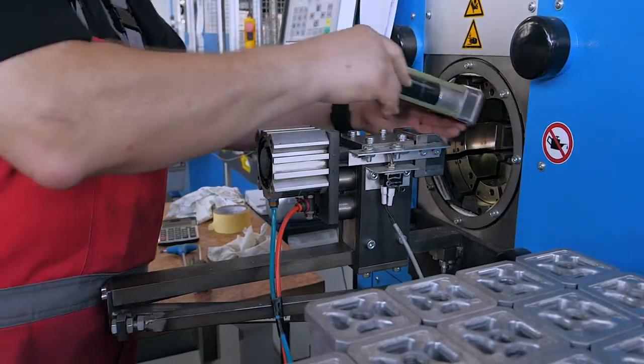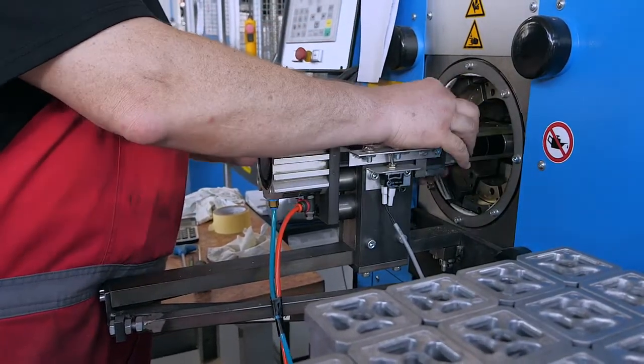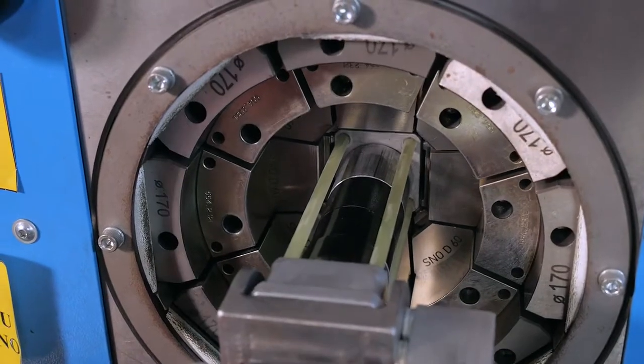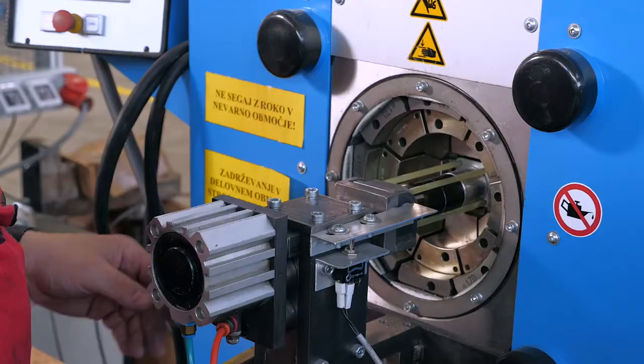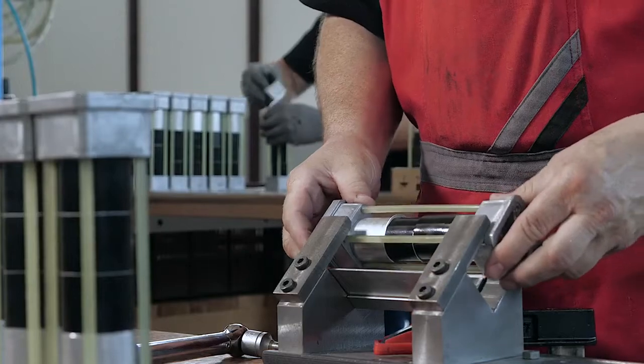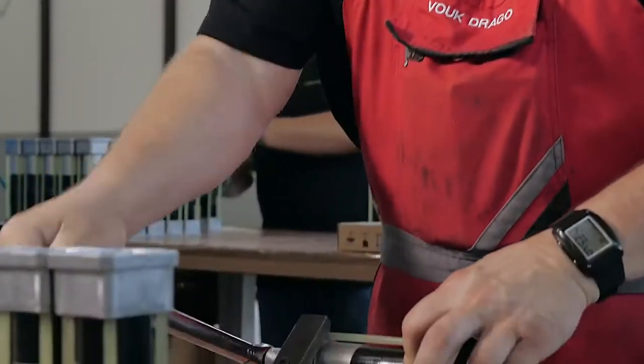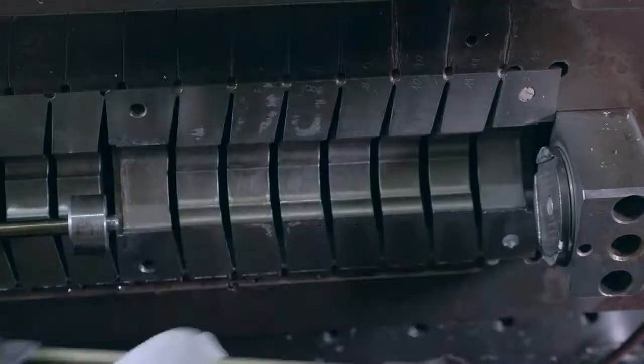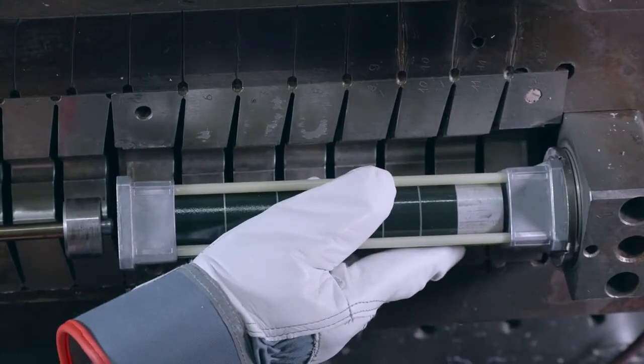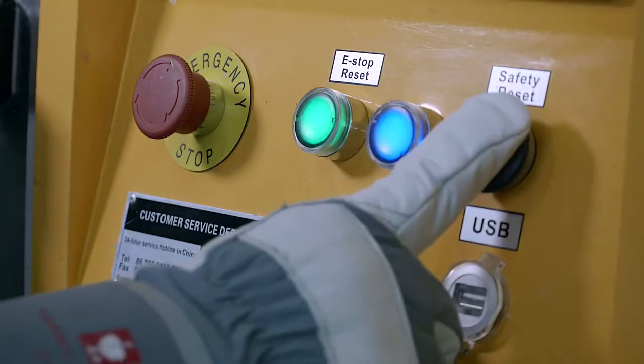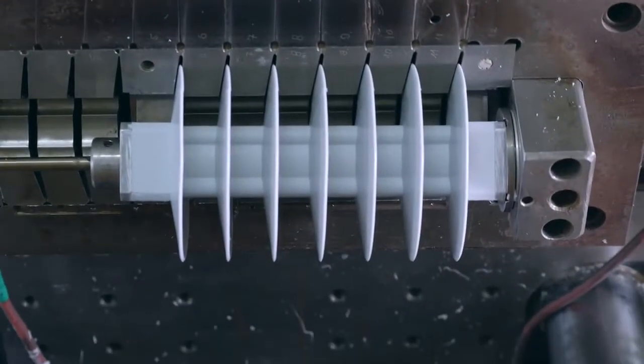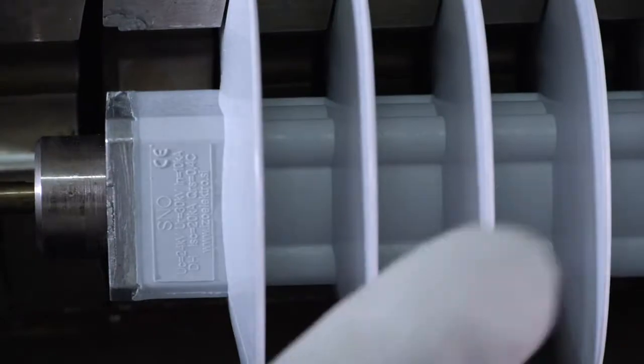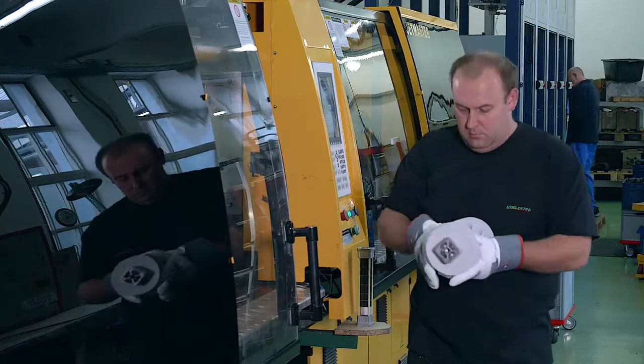Using a crimping machine, we crimp the epoxy rods onto the top and bottom fitting and tighten the varistors and the housing to the prescribed force using a certified torque wrench. The screws used in these surge arresters are made of grade A4 stainless steel. After this stage, the core of the surge arrestor is ready for siliconizing. The core of the surge arrestor is directly encased in silicone, which is a great advantage of our Class 1 and Class DH surge arresters in comparison with our competition.